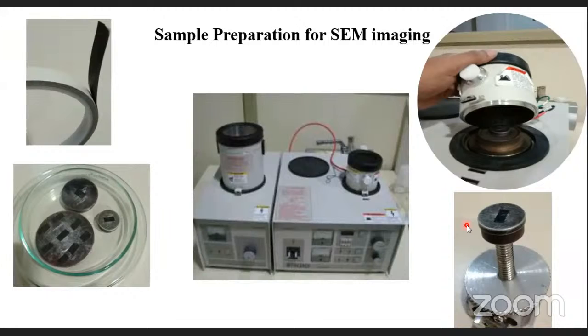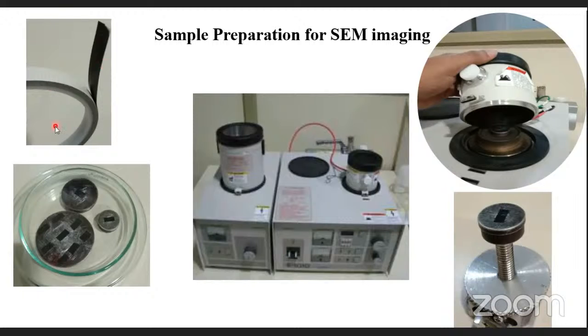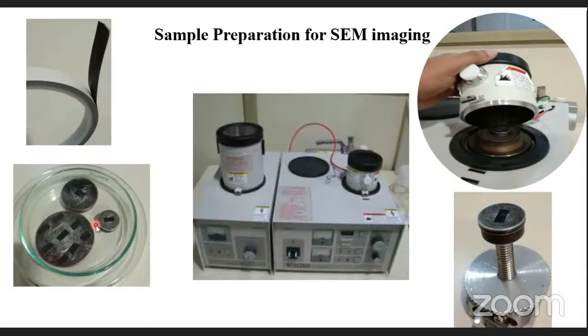If your sample is not conductive — such as biological samples, polymers, or polymer nanocomposites — we use sputtering. Sputtering means we sputter a very small thickness of gold over the sample. This is done on carbon tape placed over stubs — where we place the sample. For our instrument, the stub allows multiple samples to be analyzed; you can number them and analyze one by one.